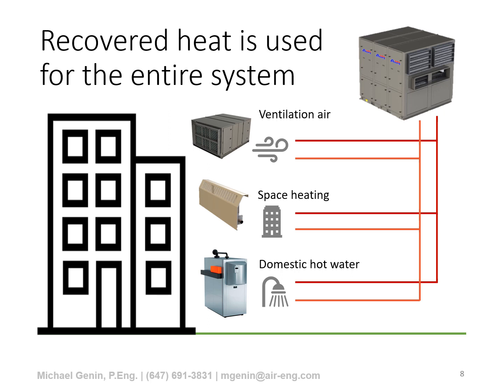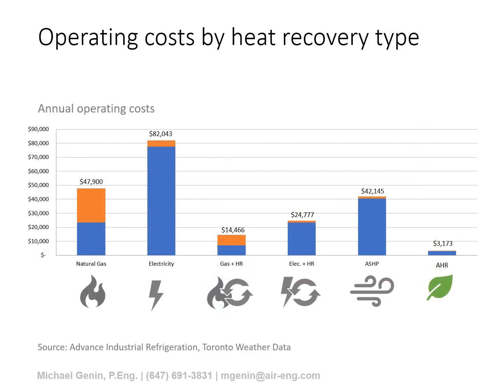This is not achievable with typical passive heat recovery devices, where they can only heat the incoming ventilation air. They're not able to heat other building spaces, and certainly not able to heat domestic hot water. So what does this mean for total operating costs? In this example, we're using Ontario gas and electric data to generate an example of a 10,000 CFM ventilation system. This might be characteristic of a 20-story office or apartment building.